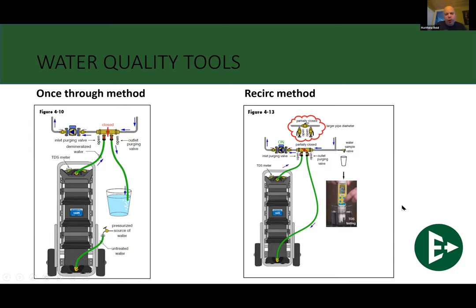Or you're getting back into that product where, again, you're looking to make the system now as best as you possibly can. You can do a recirc method through these guys. You recirc it, you run it through, pull off water samples every now and again, check your TDSs and make sure that you're going to be within your desired area that you're looking for.